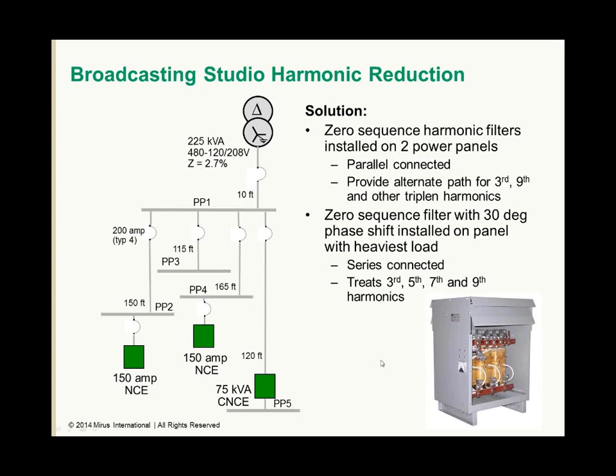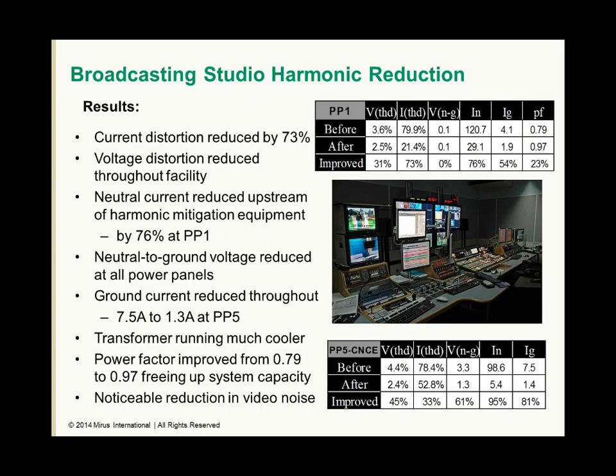Current distortion was reduced by 73%, and voltage distortion was reduced throughout the facility. Neutral current was reduced upstream of the power panels by as much as 76%, resulting in a reduction in neutral to ground voltage at all power panels. You can see here this power panel went from 3.3 down to 1.3. Ground current dropped from 7.5 to 1.4. And the neutral current dropped from nearly 100 down to 5.4.